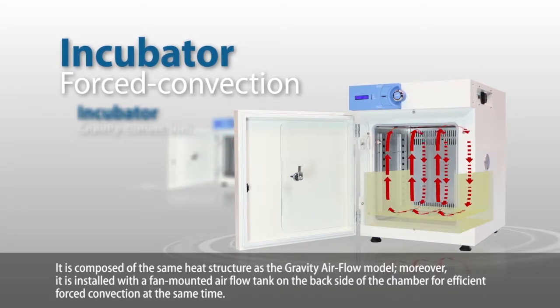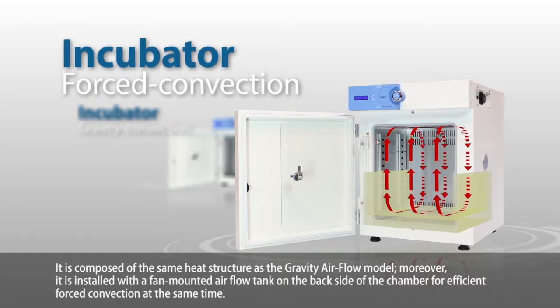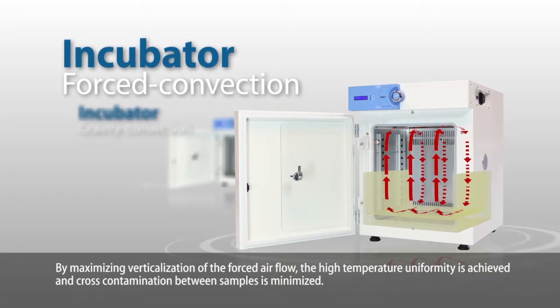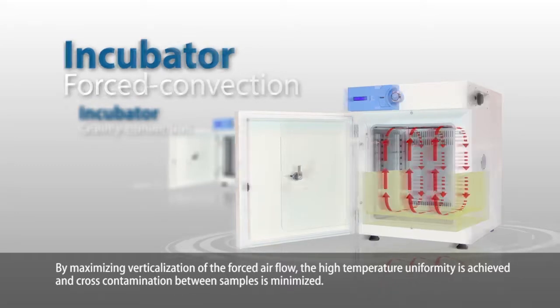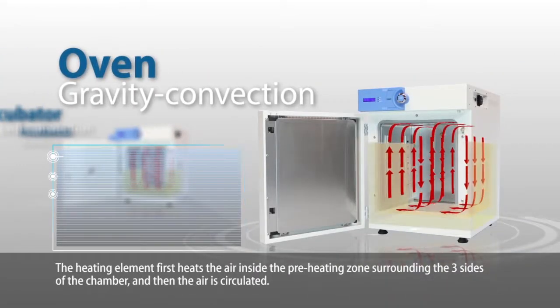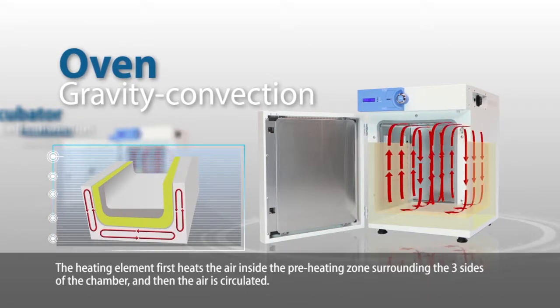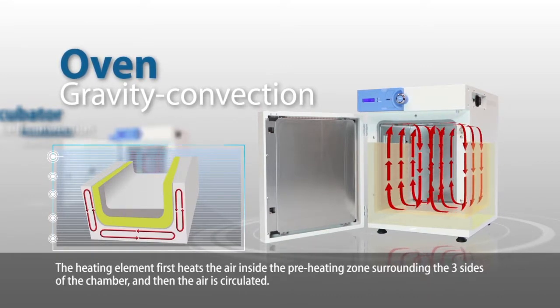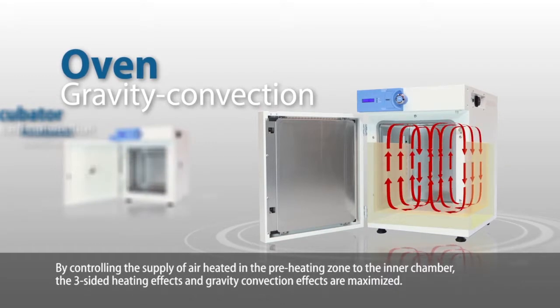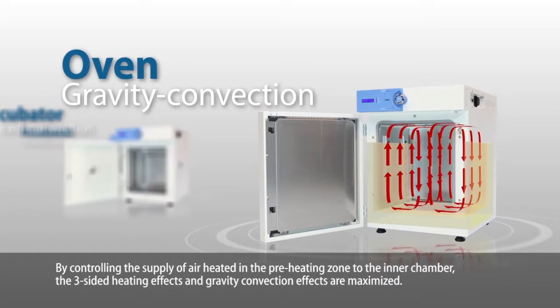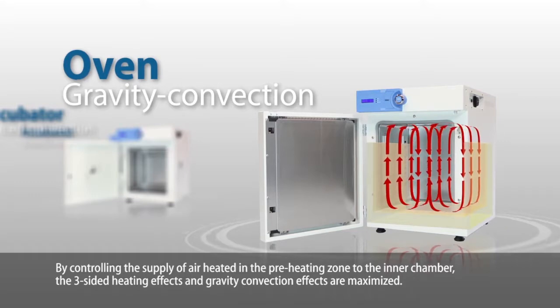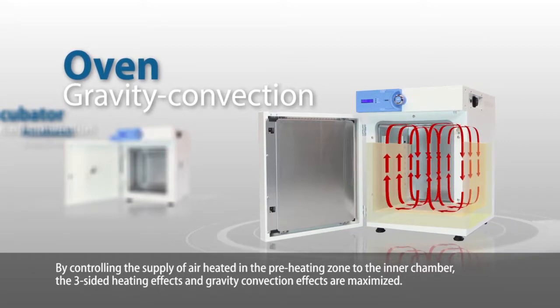Moreover, it is installed with a fan-mounted airflow tank on the back side of the chamber for efficient forced convection at the same time. By maximizing verticalization of the forced airflow, the high temperature uniformity is achieved and cross-contamination between samples is minimized. The heating element first heats the air inside the preheating zone surrounding the three sides of the chamber, and then the air is circulated. By controlling the supply of the air heated in the preheating zone to the inner chamber, the three-sided heating effects and gravity convection effects are maximized.